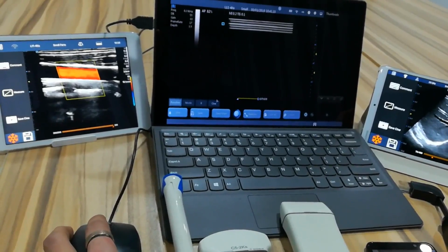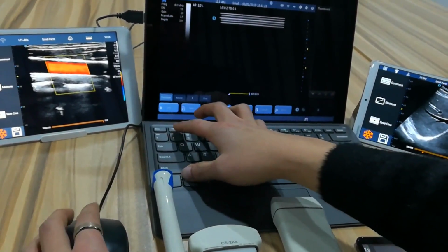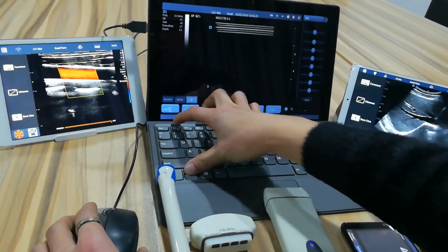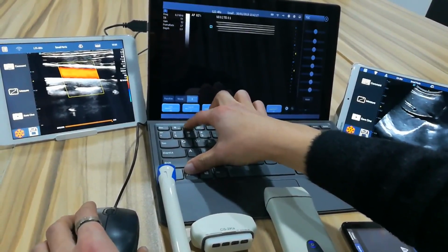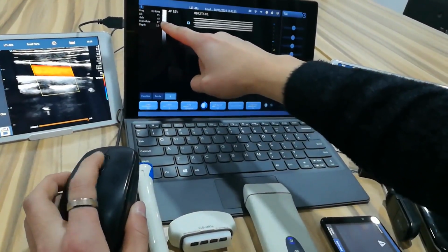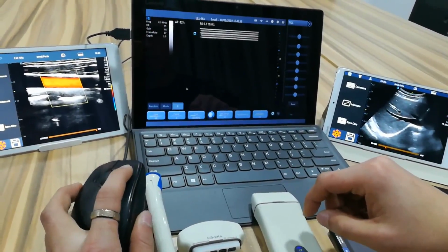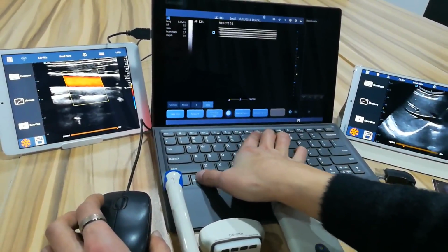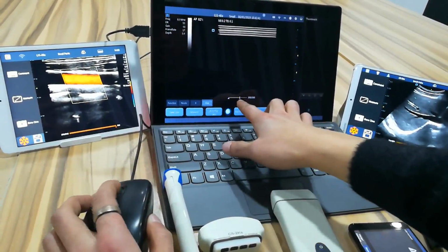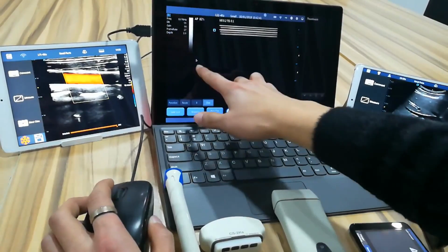And also, there are some shortcuts on your keyboard. On the keyboard, F1, now we activate images. For F1, you can change the gain, decrease it and increase it. You can see here the gain is just like scrolling up or down. And when you freeze the system, you can see the cursor. And pressing the F8 function, you can enter the system like this. And to release the cursor, you can see it again.